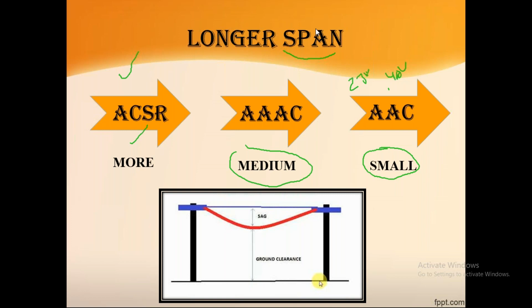Next, weight. In terms of weight, aluminum has less weight compared to copper, steel, and iron, right? Among these, ACSR has the more weight. Why? Because this conductor is aluminum plus steel, the steel reinforcement gives additional strength, that's why the weight of ACSR will be more.